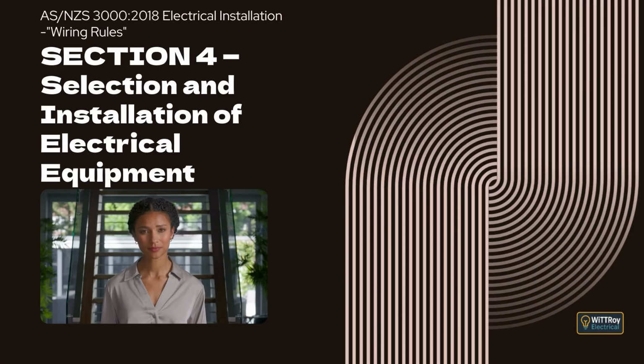Clause 4.5.1.2 Edison screw lamp holders. This clause explains that every low-voltage Edison screw lamp holder must be connected so that, where a neutral conductor is required, it is connected to the outer contact. It explains that this requirement does not apply where the lamp holder is part of an appliance installed in a permitted manner or where the luminaire and lamp holder include a shroud or skirt that prevents contact with the outer contact. Clause 4.5.1.3 Festoon lighting.